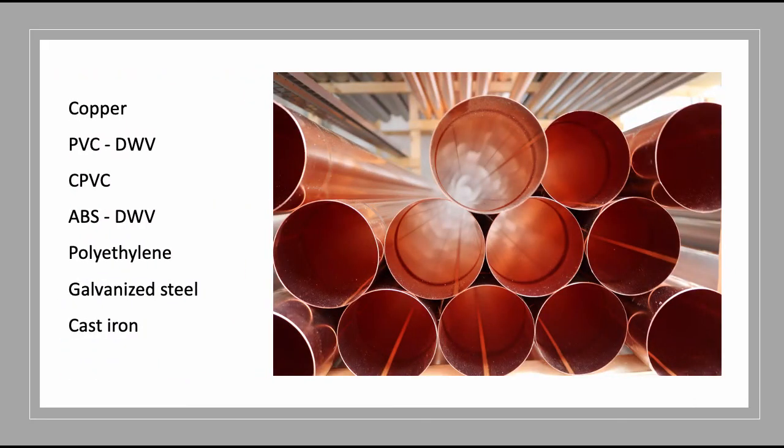The piping materials allowed are usually copper, PVC, DWV, CPVC, ABS DWV, polyethylene, galvanized steel, and cast iron. The use of short radius elbows is often prohibited. You can normally use standard fittings until you reach a certain size, at which point you may be required to use drainage pattern fittings — the DWV type.